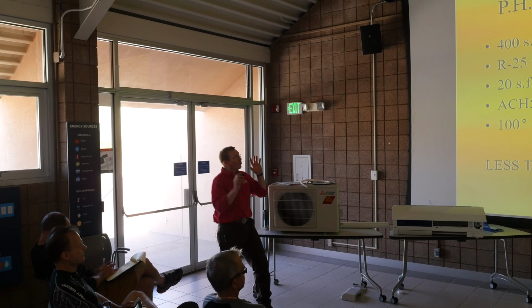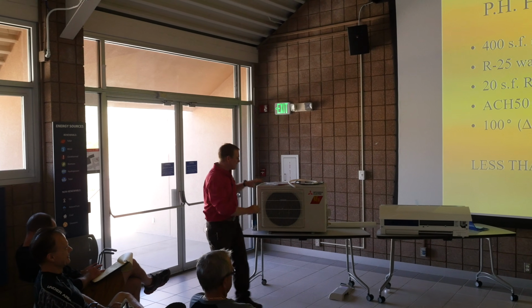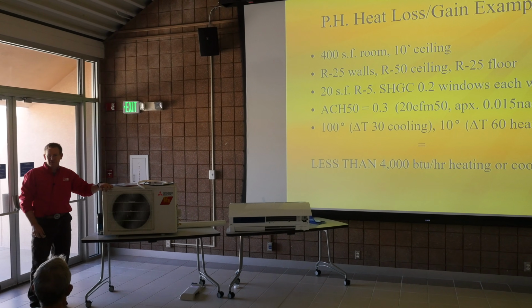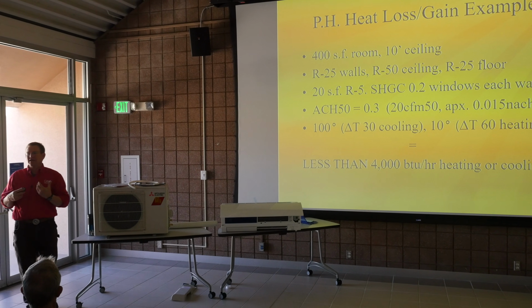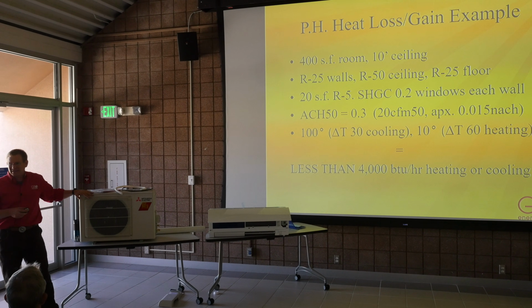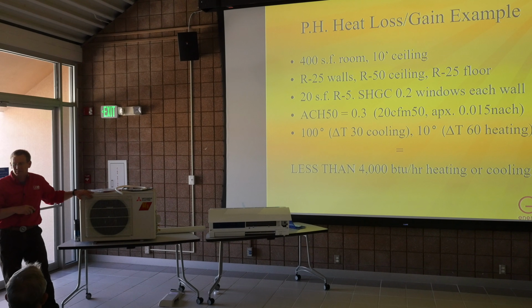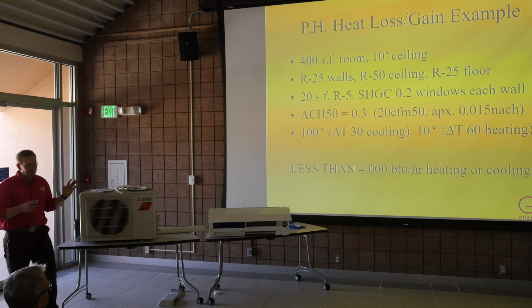So we know we want loads low. Most of these machines aren't the everyday ones we're using - they might max out, and yes, we have the ability to do 500,000 BTUs, but the average residential system size is about 50,000, maybe 60,000 or less. A well-built home, no problem - I can do 4,000 to 5,000 square feet with 50,000 BTU. But I can't do my 1904 cinder block home with 50,000 BTU - I need 150,000. So simple stuff.